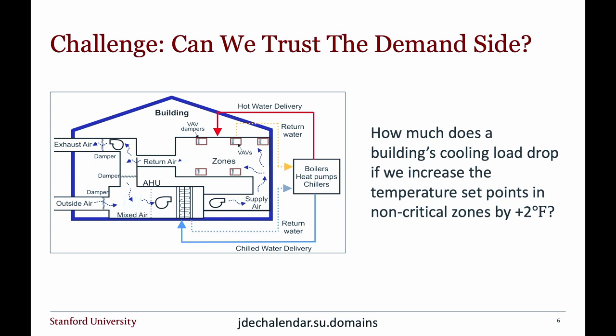So the first question I want to start with is, if I go back to this picture of this building, I want to answer this question: how much does the building cooling load drop over the course of a day if I increase the temperature set points in all the non-critical zones in the building by 2 degrees Fahrenheit? And why is answering that question not so trivial?